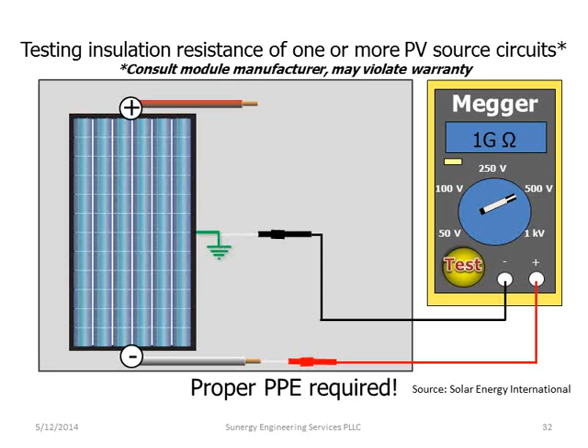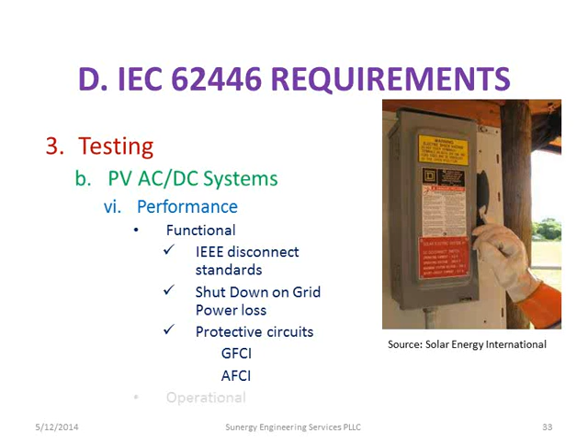And then the final thing in testing is just to make sure that everything's working, make sure that the inverter shuts down when the power goes off, make sure that the ground fault is working. Basically, that's pretty easy to do. You take the ground fault fuse out and you start the inverter up. Shouldn't start, right? And then if there was arc fault, we'd have to do a test on that too. That's coming sooner or later.